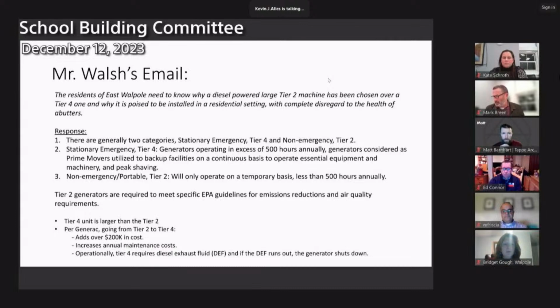Generators considered as prime movers are utilized to back facilities on a continuous basis to operate essential equipment and machinery and/or peak shaving. And again, that's a generator that would be used to offset utility costs. They would run it for hours on end to offset higher utility cost. The non-emergency portable tier 2 will only operate on a temporary basis, less than 500 hours annually.